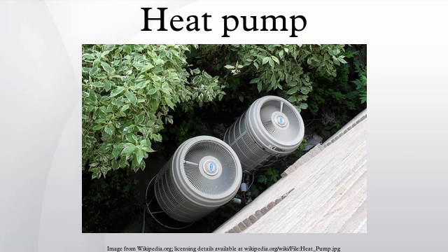Heat distribution. Heat pumps are only highly efficient when they generate heat at a low temperature differential, ideally around or below 32 degrees Celsius. Normal steel plate radiators are not practical, because they would need to be 4 to 6 times their current size. Underfloor heating is one ideal solution. When wooden floors or carpets would spoil efficiency, wall heaters and piped ceilings can be used.